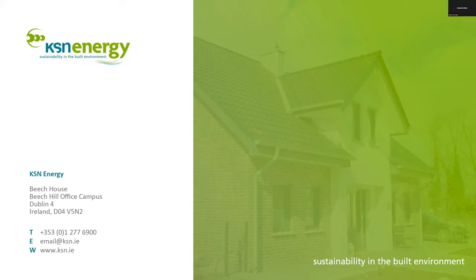And I had the other question: the other 20%, what's the assumption on that? Is that coming from an immersion? Typically generated by an immersion. Okay. And as we see with the development in refrigerant, newer heat pumps coming in the future can deliver 100% of the load for the hot water. But as part of SEAI's grant, they only ask that it delivers 80% as a minimum. Okay, understood.